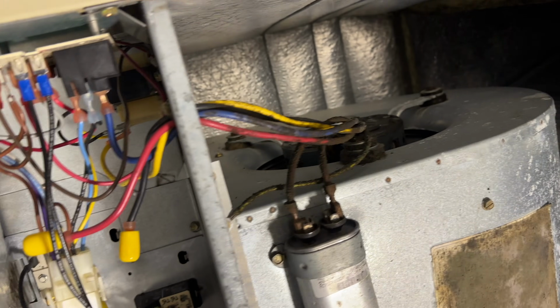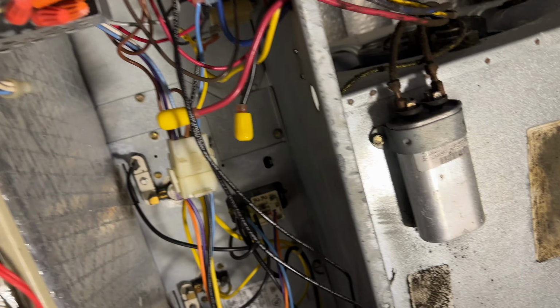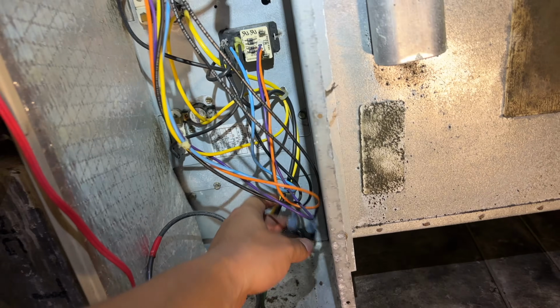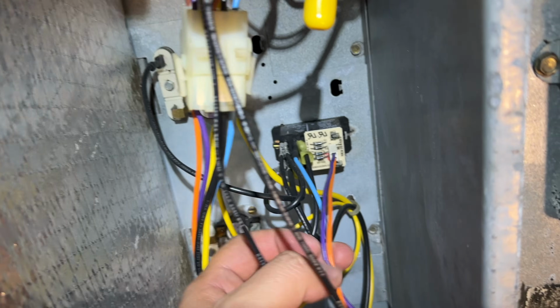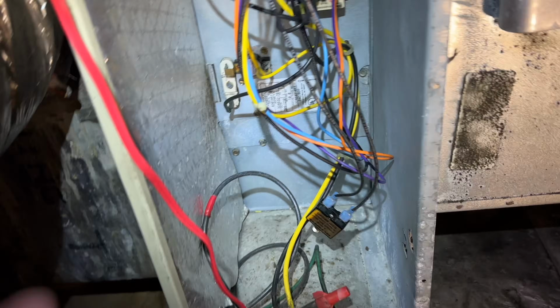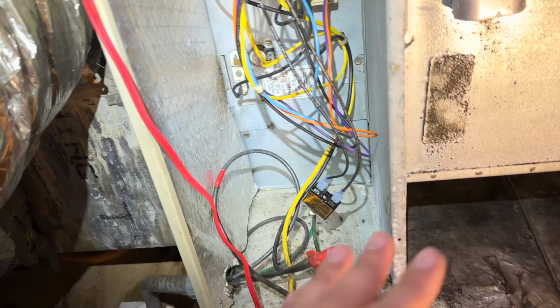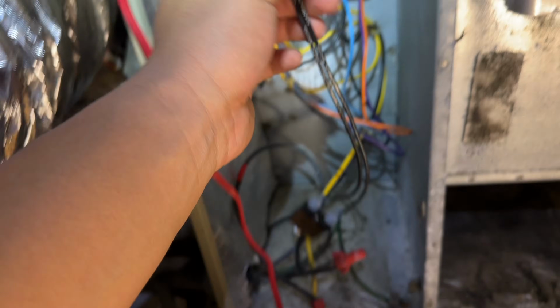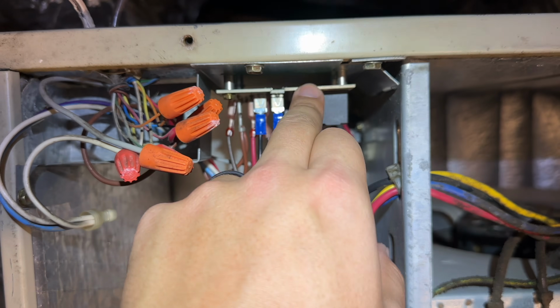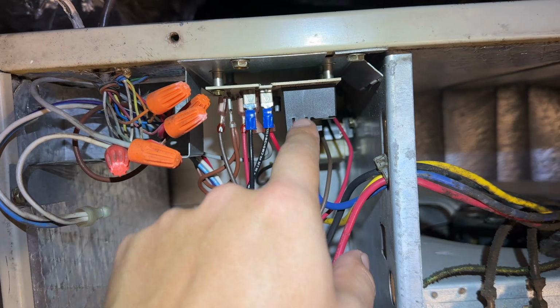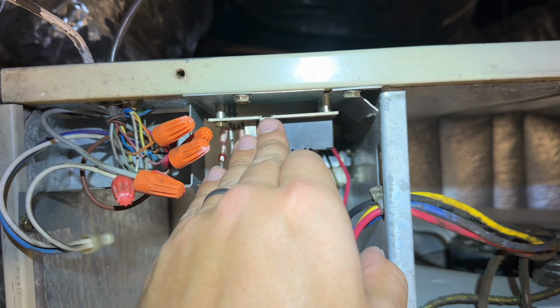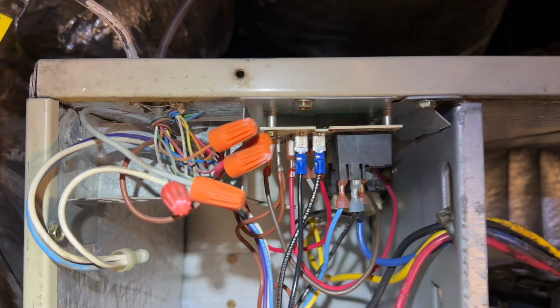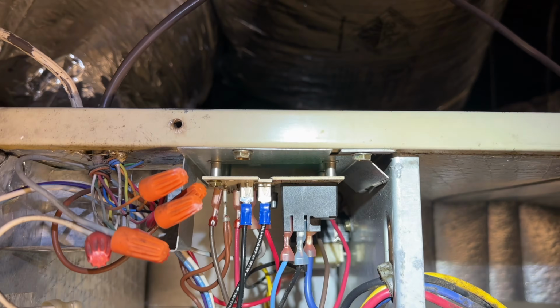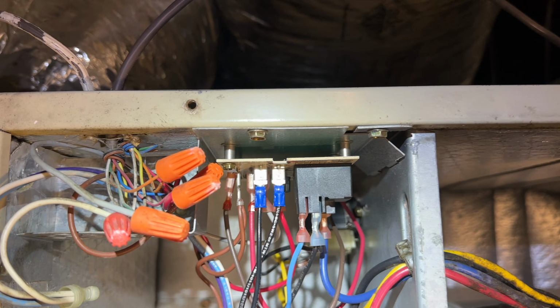Let me look into this a little more, see what wire it is. Okay, so I've been looking for about 5 minutes. It did trip again. I tried pulling this out just to eliminate an option, but when I went to plug it back in, it still tripped. So I untripped it, have it disconnected again. But I think I'm gonna go ahead and check this little control board right here. Sometimes it could be these little relays or something shorted to ground on the actual control board. Let me look at that and see if I find any burn marks or anything like that.